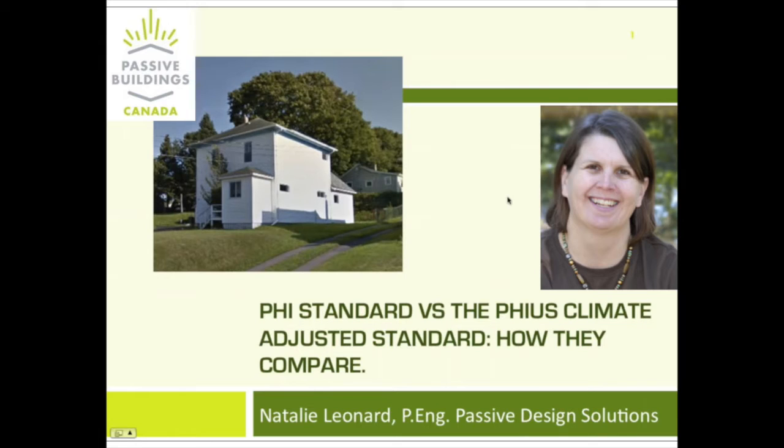We monitored the Hawkins passive house for about 2 years, and it definitely showed that the heat load was quite low in the house, and the electrical usage was higher than the house was certified to the PHI standard.